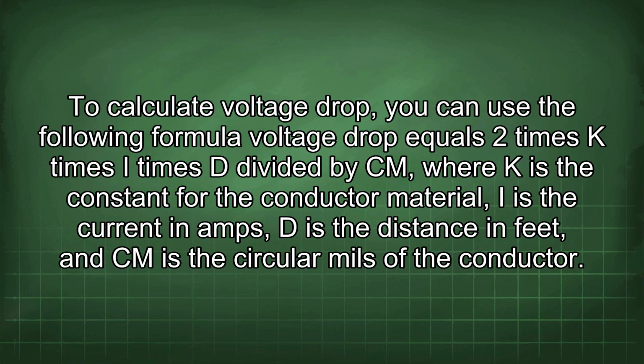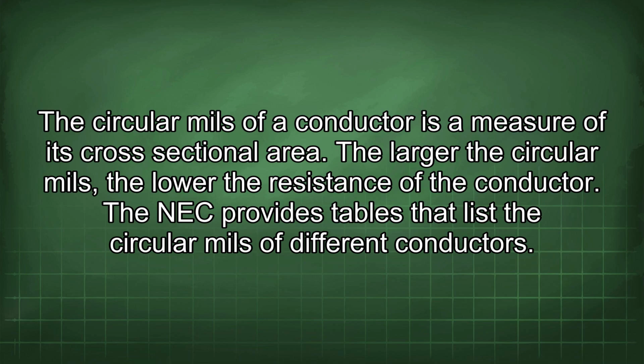To calculate voltage drop, you can use the following formula: voltage drop equals 2 times K times I times D divided by Cm, where K is the constant for the conductor material, I is the current in amps, D is the distance in feet, and Cm is the circular mils of the conductor. The circular mils of a conductor is a measure of its cross-sectional area. The larger the circular mils, the lower the resistance of the conductor. The NEC provides tables that list the circular mils of different conductors.